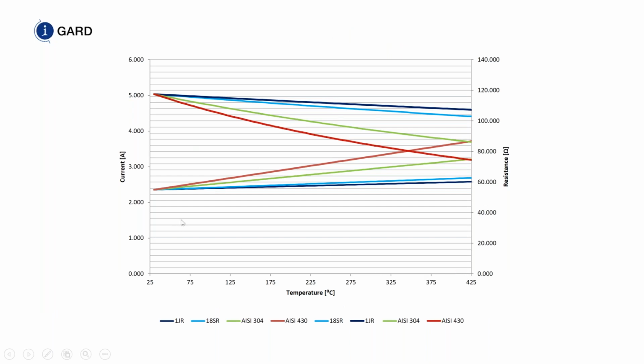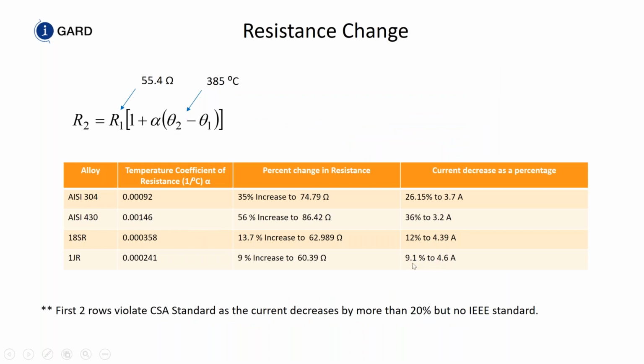So this is what it looks like graphically. We start with 55 ohms, and we increase our temperature to 385 degrees C above ambient, and our resistance increases, our current decreases. So we want to have the most stable current you can have for a high resistance grounding system. That's why we use the most effective material, which has the most consistent temperature coefficient of resistance, and the resistance changes from 55 ohms to 60 ohms. Very stable.